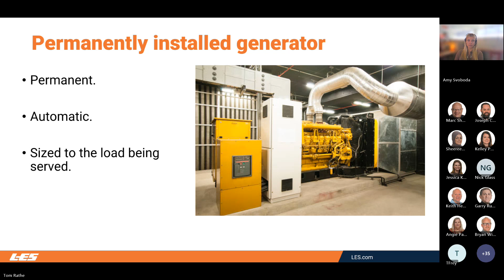The pros of this is it's always there, always ready to go when needed. Nobody's going to borrow it because it's hardwired and bolted in place. It doesn't walk away. It provides power to the critical loads within seconds of the utility power going out, so power is restored typically in less than a minute. You own it, you maintain it, you know its service history, you assure its readiness and reliability, not someone else.